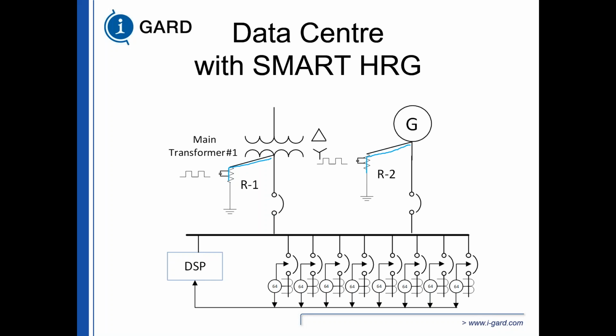More often than not, ground faults occur in the loads, not in the sources. So we could have our ground fault sensing equipment with a feeder module on each separate feeder, telling us where we have the fault. The ground fault doesn't care whether we're being fed by the generator, in which case it would take this route back, or whether we're fed by the transformer, and take this route back to the source. Ground faults always have to return back to the source.